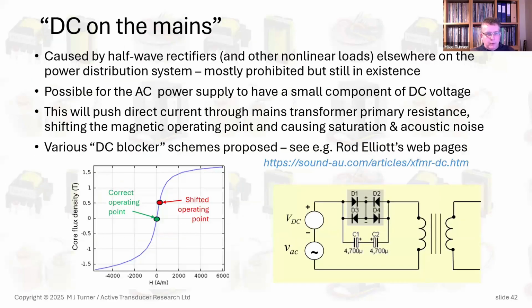One last point about transformers used for power supplies. In the old days, and some of you may remember this, a lot of you probably won't, TVs and radios had half-wave rectifiers in them because they were cheap, and they also, once upon a long ago, allowed connection of the equipment to a DC power supply as well as an AC one. And that used to cause direct current components on the mains supply, and therefore a standing voltage. If you put your Fluke meter across the socket, you might see a fraction of a volt of DC as well as the 250 volts of AC. And that low voltage DC will push current through the transformer primary. It shifts up the operating point, as you can see in the graph here, and that means we bang our heads against saturation in one direction earlier than we otherwise should, and that again causes noise.